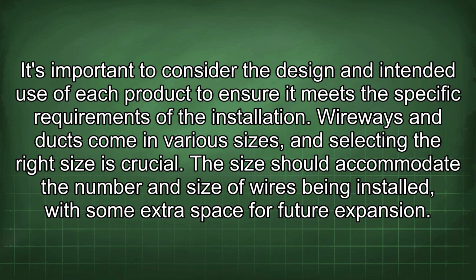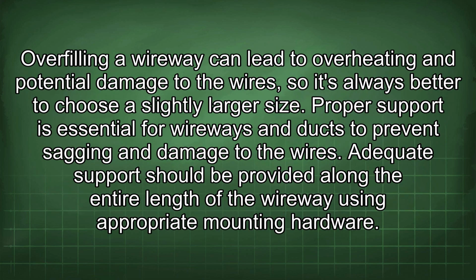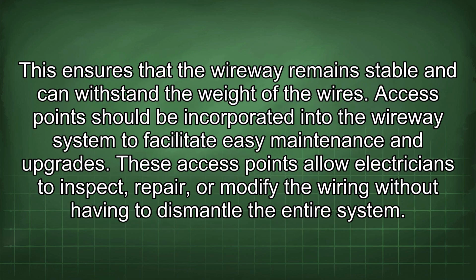Wireways and ducts come in various sizes, and selecting the right size is crucial. The size should accommodate the number and size of wires being installed, with some extra space for future expansion. Overfilling a wireway can lead to overheating and potential damage to the wires, so it's always better to choose a slightly larger size. Proper support is essential for wireways and ducts to prevent sagging and damage to the wires. Adequate support should be provided along the entire length of the wireway using appropriate mounting hardware. This ensures that the wireway remains stable and can withstand the weight of the wires.